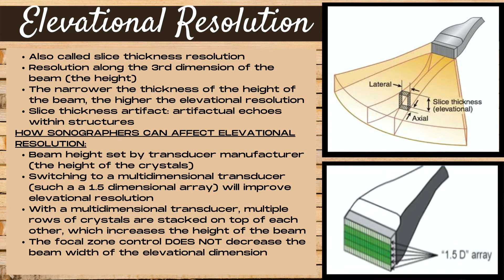Elevational resolution, also known as slice thickness resolution, is resolution along the third dimension of the ultrasound beam — the height of the beam. The narrower the beam thickness, the higher the elevational resolution. Slice thickness artifact creates artifactual echoes within structures. The beam height is set by the transducer manufacturer. Switching to a multidimensional transducer, such as a 1.5 dimensional array, improves elevational resolution by stacking multiple rows of crystals. Note that the focal zone control does not decrease beam width in the elevational dimension.